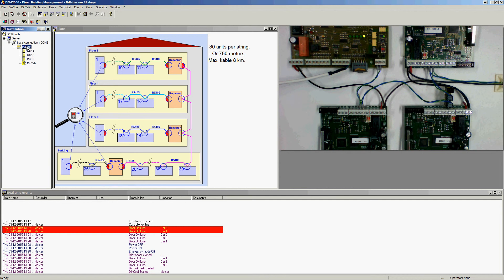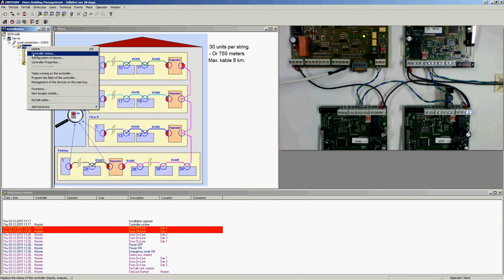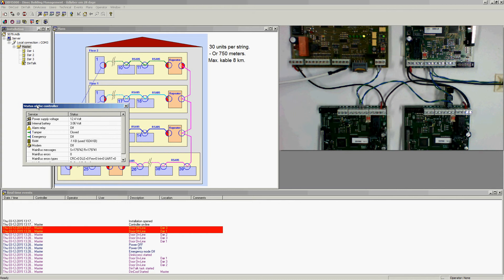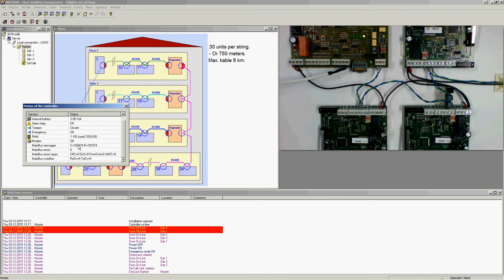What we have to do is press Ctrl+Shift and then right-click at the controller status. Now we have a few other columns revealed. The most interesting is of course this one, which is called the main bus error. We have packages sent and received by the controller. If something is going wrong with a door, the signal or packages from the door will be missing and then the main bus error indicator will start counting.